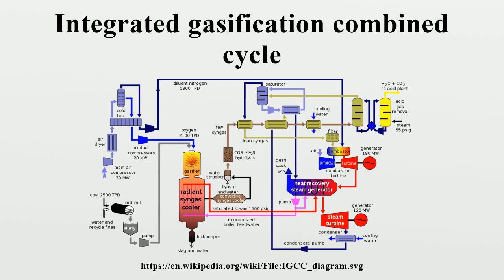Third, unplanned downtime on the gasifier because of refractory liner problems, and those problems were expensive to repair. The gasifier was originally designed in Italy to be half the size of what was built at Polk. Newer ceramic materials may assist in improving gasifier performance and longevity. Understanding the operating problems of the current IGCC plant is necessary to improve the design for the IGCC plant of the future. Keim, K. 2009, IGCC project on sustainability management systems for plant redesign and reimage. This is an unpublished paper from Harvard University.